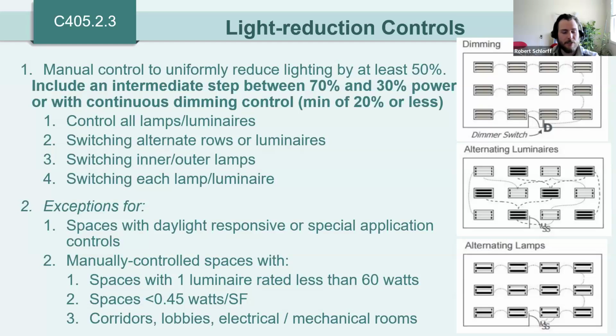And that also, as I mentioned earlier, is another instance where the IECC is becoming more aligned with ASHRAE 90.1. There are exceptions listed below here that generally apply to spaces or configurations that don't really allow for uniform dimming, or if the control isn't cost effective within that space.